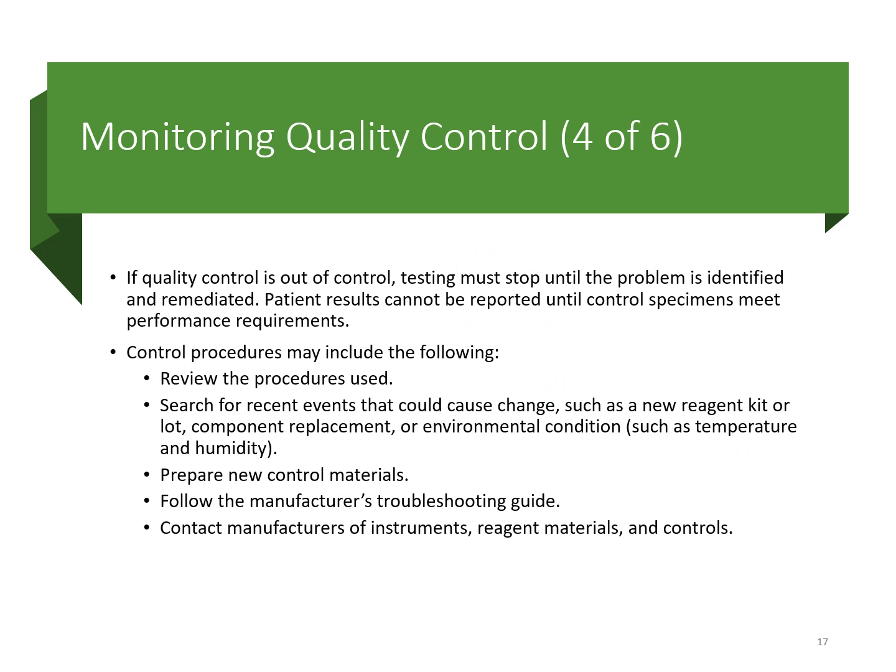So if you run quality control and it violates any of the rules that are set forth for your laboratory or QC rules in general, then that flags you that, hey, my quality control material is not giving me the results that I expect. So therefore, if I run my patient, those results probably aren't accurate. So maybe I need to look at a few things, not run those patients until I make sure that my analyzer is performing as required or as expected.